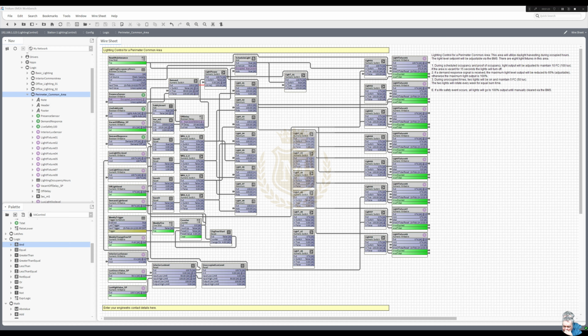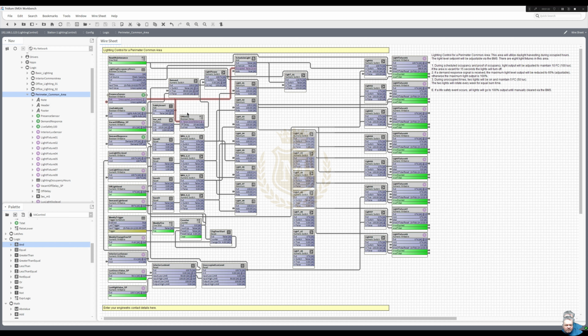And that would work. So we're occupied. That's unoccupied. We're still 100%. That's now false. Now we're going to 0 after the time limit of 15 seconds.